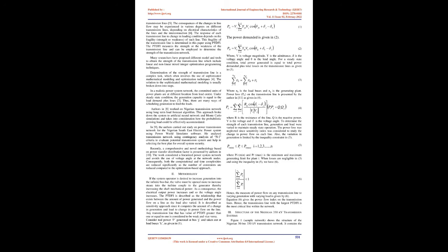This implies that none of the transmission lines or cables is overstressed, and voltage magnitudes and voltage angles are not violated. If the thermal loading limit of a transmission line is exceeded, it will lead to an increase in conductor temperature. This will increase the sag of the transmission lines between the towers, and if not checked, may result in irreversible stretching. Therefore, such lines are described as critical and overstressed.